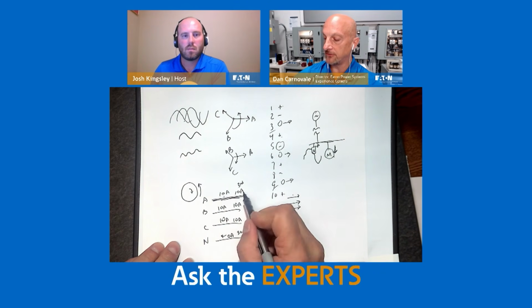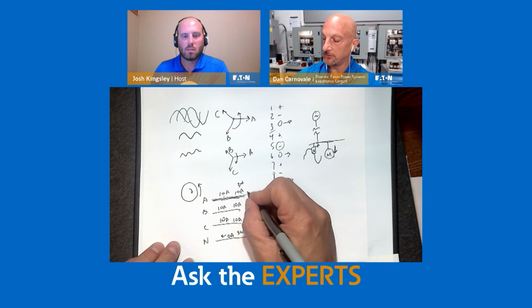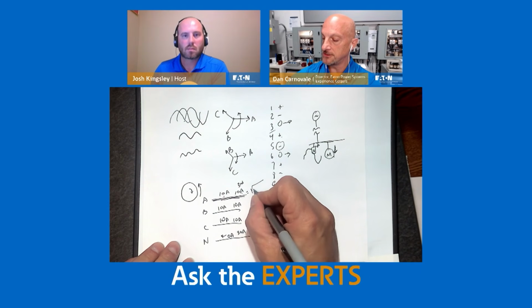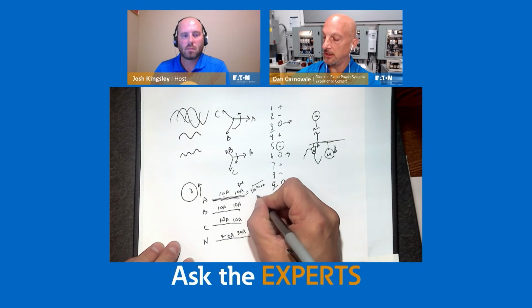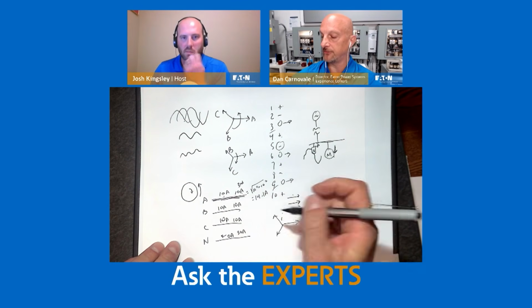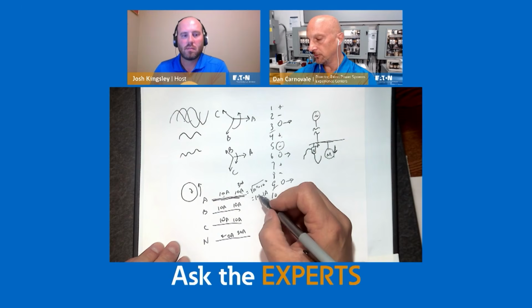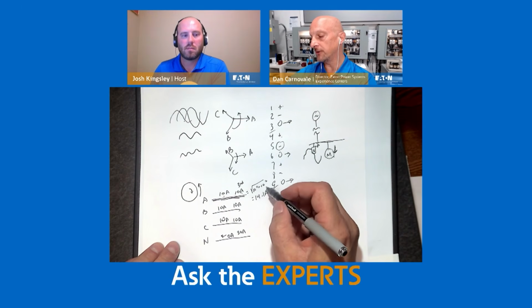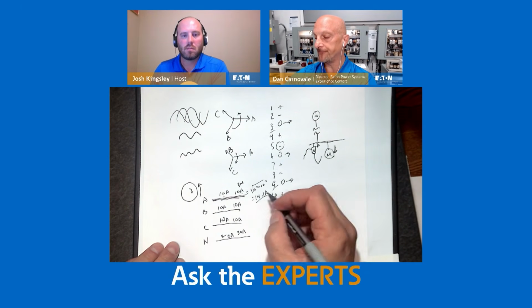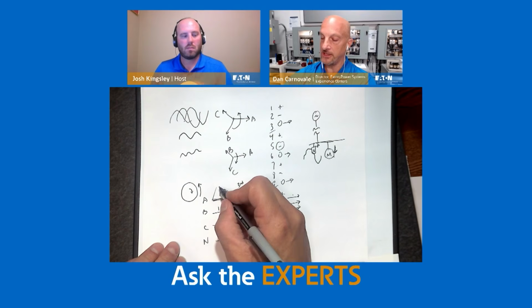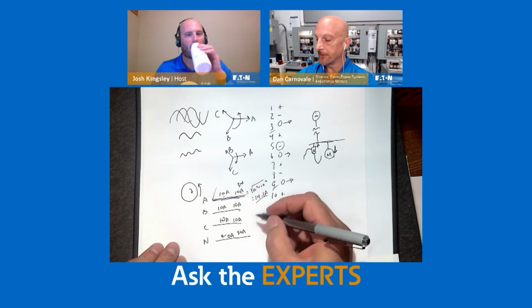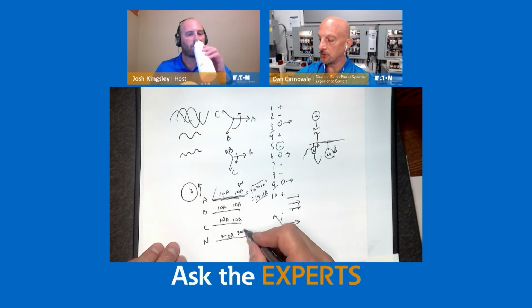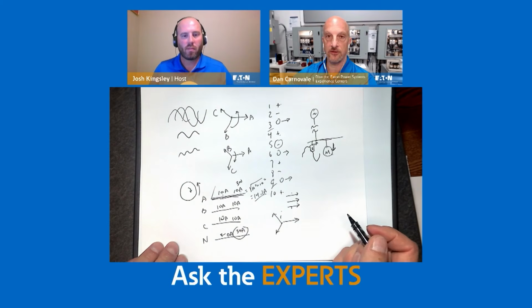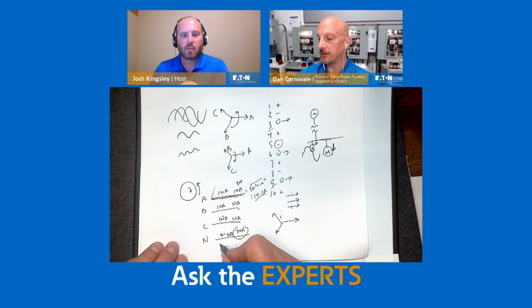Now, if you look at what this phase wire is going to be rated for, it's going to have 10 amps plus 10 amps, but you do that in an RMS fashion. So it's 10 squared plus 10 squared, and that's going to be 14.1 amps. That's square root of 2, by the way. So it's 14 amps on phase A. That could be a 20 amp wire, 12 gauge wire. If I use 12 gauge wire in my neutral, it's only rated for 20 amps. I have 30 amps, so I'm going to burn up my neutrals. That's why they double the neutrals.